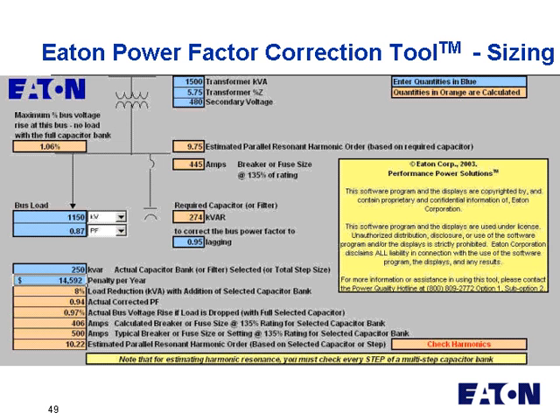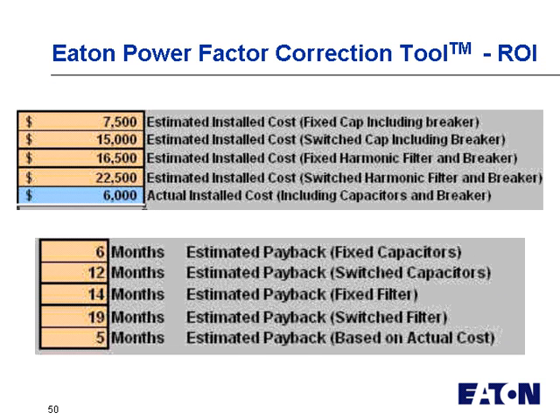Now again, sizing the capacitor bank or other power factor correction solution is important to this whole process, because you need to come up with the right size, not too big, not too small, and also avoid resonance issues. And this power factor correction tool has another page that we use to actually put in system data and sort of do a small model of the system to both look at what size capacitor bank or harmonic filter, for example, should be used, and really what is the target power factor so we can apply the right solution. This also looks at harmonic resonance points with a given transformer size and impedance so that we can understand what we need to avoid.